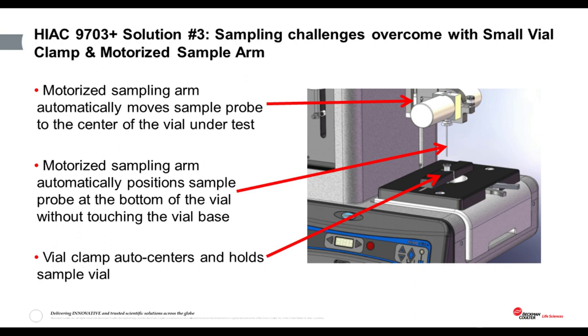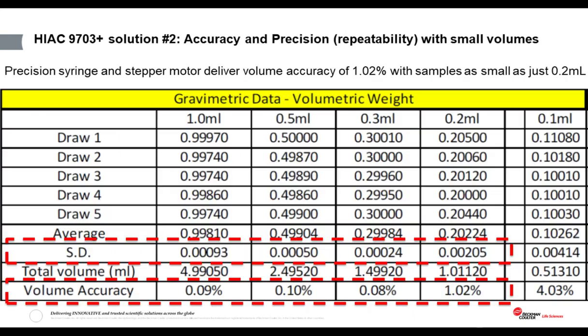Secondly, the HIAC employs a motorized sampling arm controlled by a precision stepper motor, so it's automated. And this ensures that the probe is inserted accurately into the center of the vial and as close to the base of the vial without touching the bottom of the vial. Additionally, the HIAC has a vial clamp, which holds the vial in place during the test and ensures that the vial is centralized under the sampling probe. And this eliminates the variability that would be introduced should the technician have to hold the vial by hand.